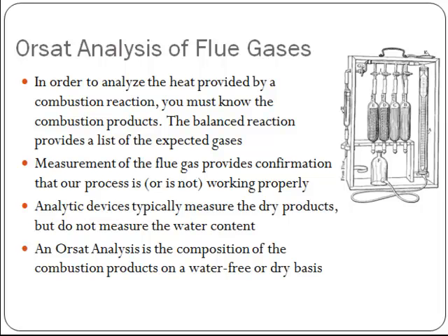Maybe a little hole on the fuel injector gets plugged, and so you're not getting quite the pattern that you had before. And so therefore you're going to want to measure not only what's going into this furnace, but you also want to measure the products, the flue gas, the exit gas out of the furnace or this combustion chamber.